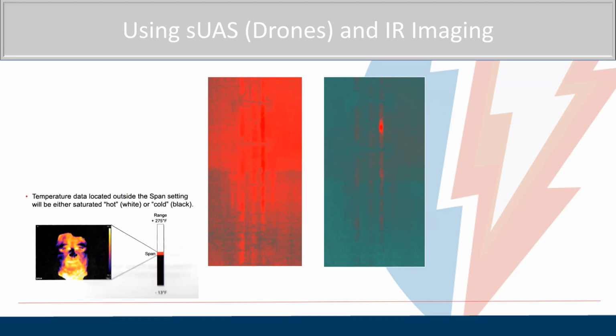I wanted to talk a little bit about post-processing, and this is an example of setting the range so that you can actually see what you're interested in seeing. The photo on the left, that big red one, is a picture of the tower that's unstretched. If you stretch the image to get rid of some of the areas that you're not interested in, like the sky background, you can see that there is a thermal gradient there. And again, this is that same picture I showed you with the problem on the transmission line. You do this by adjusting sliders in the software so that you're looking at a much narrower range of temperatures, rather than trying to look at the sky and the tower, which doesn't give you much information about what you're looking for.